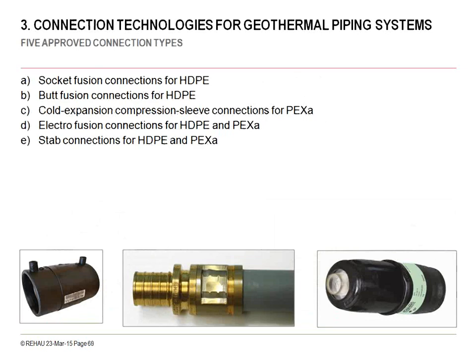I'm going to move now over to some of the joining methods of the Hdpe and PEX pipes. The Hdpe is typically fusion. I mentioned it's a thermoplastic, and so it would be heat fusion with heat plates in the range of about 500 degrees Fahrenheit. So you have socket fusion, butt fusion. You can also have electrofusion and stab fittings with the Hdpe pipes. The cold compression fitting system for PEX pipes, which is the center image, which is the one that is from RAUGEO, cannot be done with the Hdpe pipes.